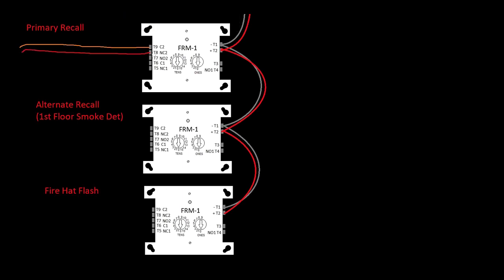Now I think I've gone over these relays but just in case I haven't, this style, the System Sensor style of relay, has two sets of contacts. So you can see we have common two, normally closed two, normally open two on the top there, and then you have common one, normally closed one, normally open one over here on the right. Those are just two different sets of contacts, so in most cases you'll only use the one side.